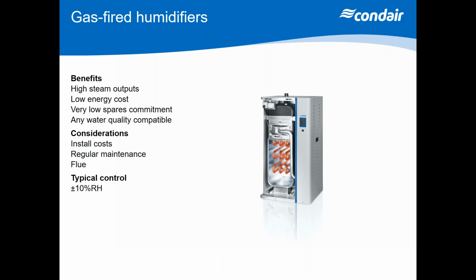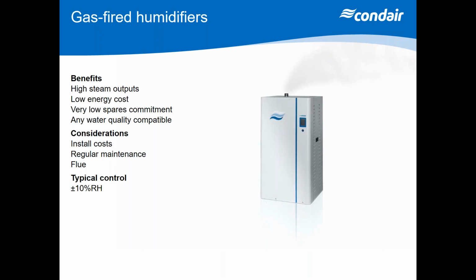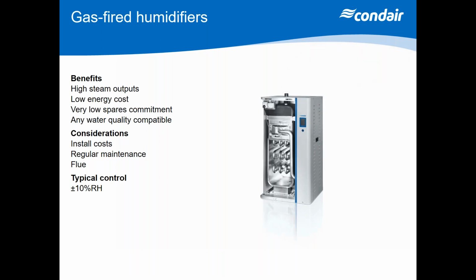Pretty straightforward. We control the output by varying the burners, so we do get typically plus or minus 5 to 10% RH control. And for applications such as a spray booth or something like that, it's very common to use gas because we get consistent high demand levels and high airflows, so high steam duties. So the run cost for using gas is better than for using electricity. They start though about 15 to 20 kilograms an hour and go up to 260 kilograms an hour, again lending themselves to those larger duties.